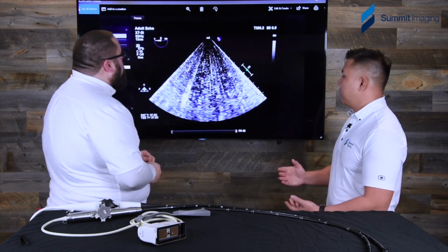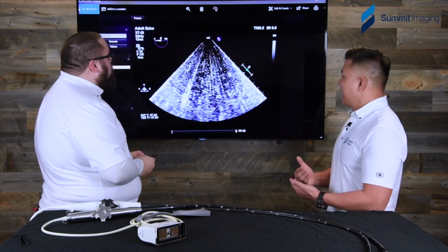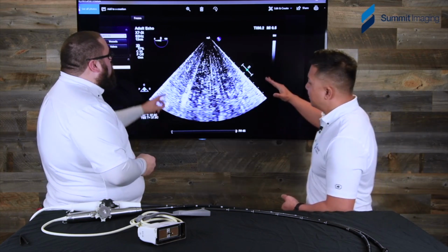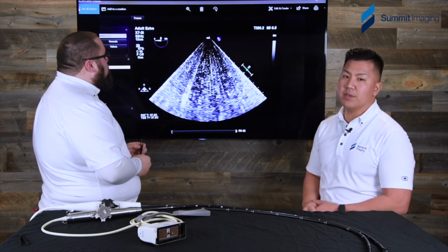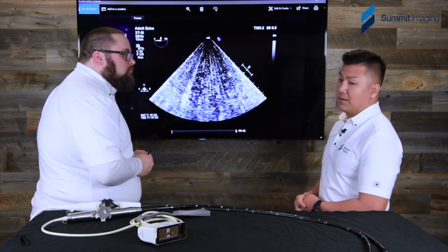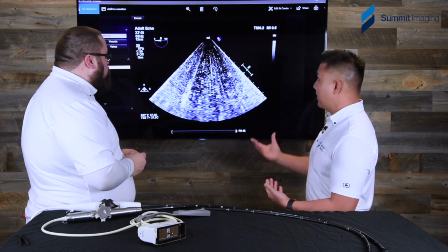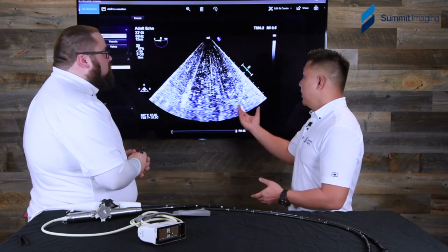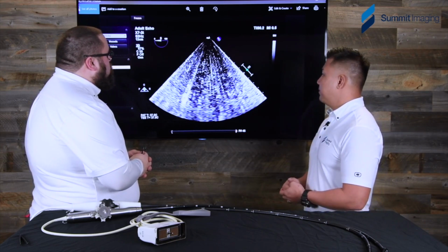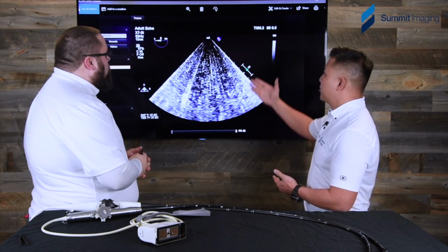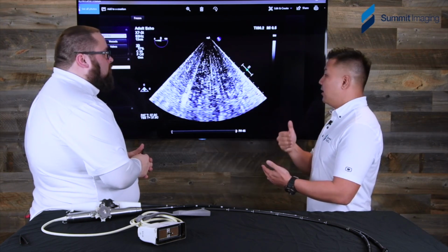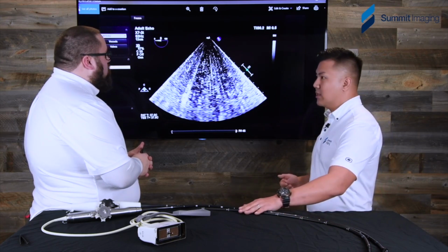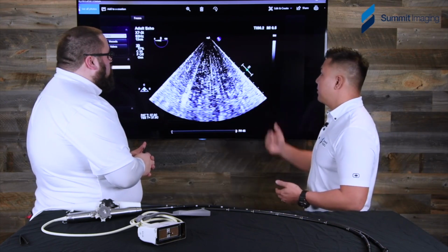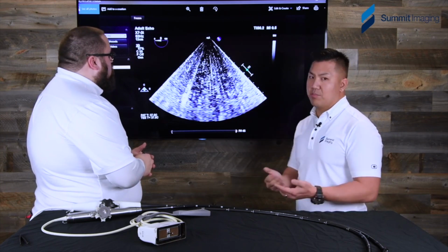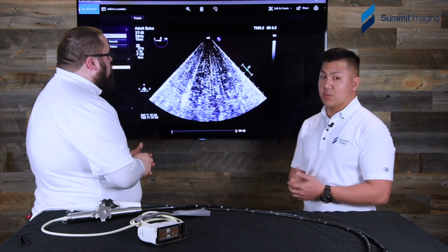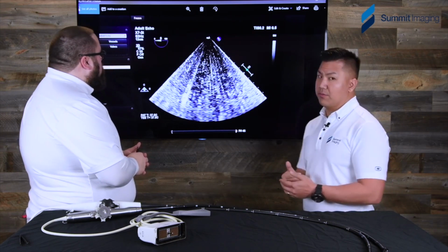So I think this is an example of a probe that's pretty far gone, and you're seeing a ton of noise across the entire image, which means there's been significant degradation of these circuits, likely at the crystal. Could be anywhere in the transducer, but in our experience, we've seen a lot of this. There's so much damage at so many of the interconnects from the lines inside the probe that go to the crystal that this is going to be a tough one to recover. At this point, this probe is likely unrepairable. There are instances where you can recover from this, but the odds aren't in our favor when you see this on your screen.